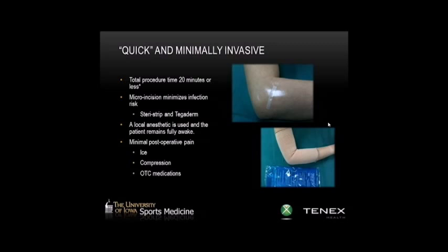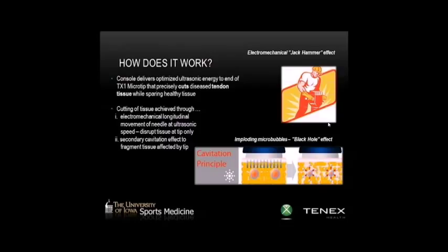So how does it work? Basically there's two ways to think about this. One is what I call the jackhammer effect. This is just the electromechanical effect of the tip vibrating, basically causing disruption of the tissue right at the tip from the longitudinal movement.